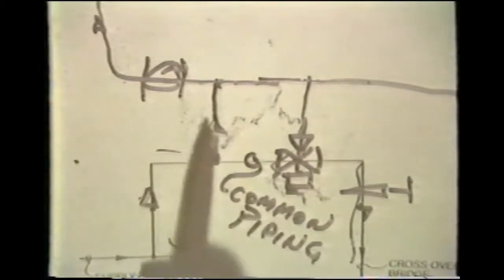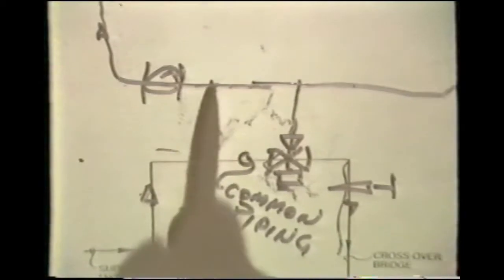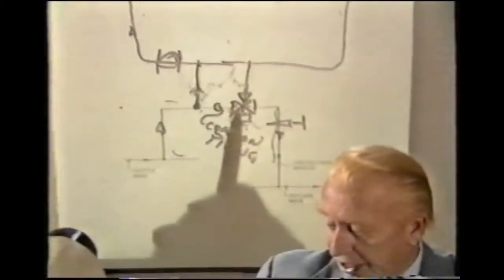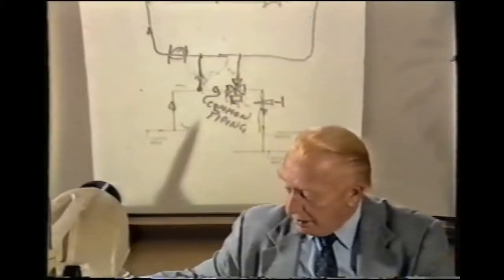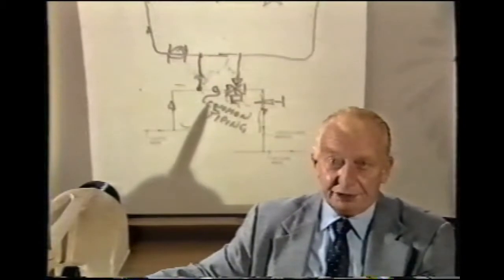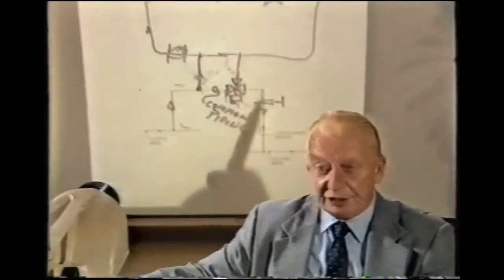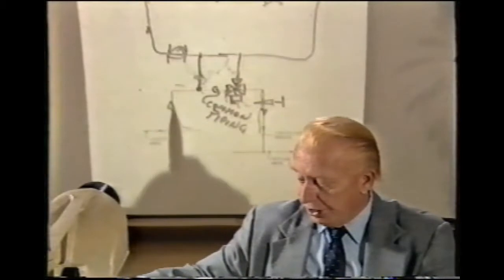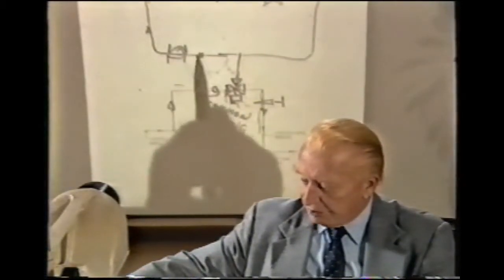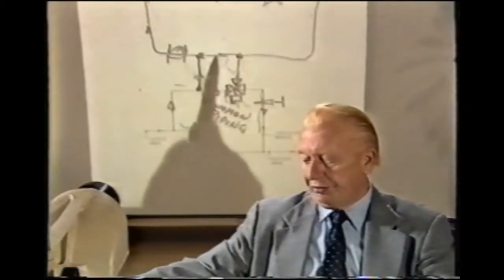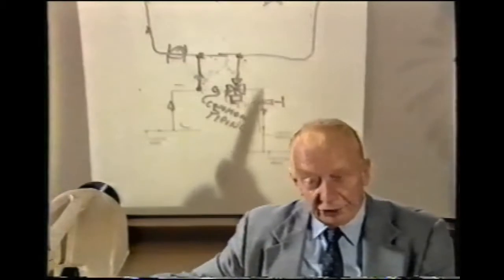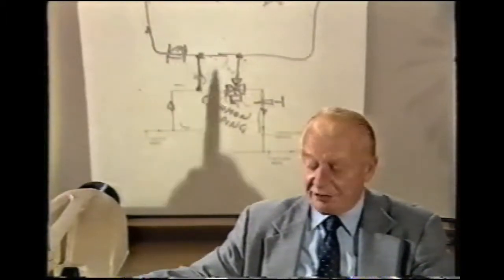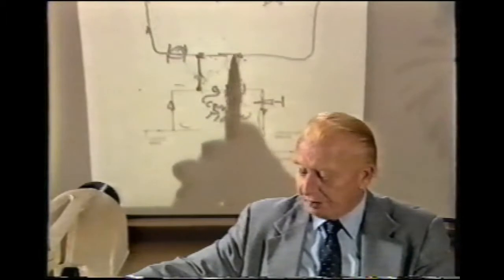And what we're doing with this then is to change the flow rate introduction from the primary circuit and into the secondary circuit by operation of the control valve. This has been illustrated for the single pump, for the injection pump, and now for three-way control valves, with the three-way control valves again generally being applied as a mix valve in the crossover bridge itself, and our common piping change is now from the crossover bridge and into the secondary circuit. It will be noted, however, that we still have the disassociation of pumping of the secondary circuit from the primary circuit because of the very low pressure drop in that common piping.